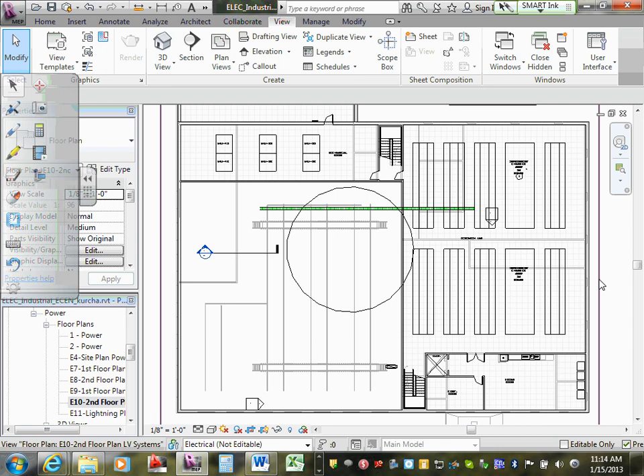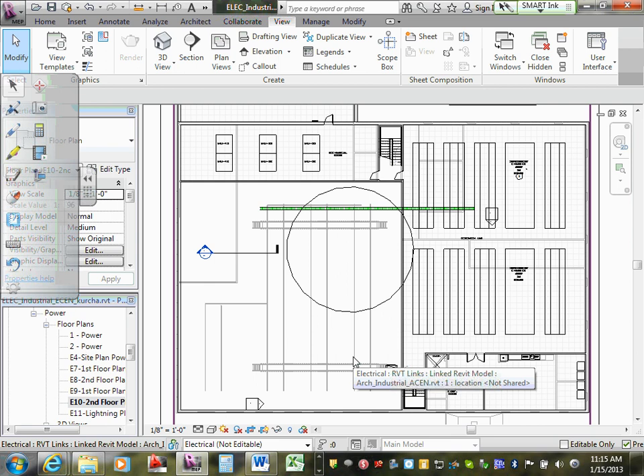Usually it's tied into the building automation, it's tied into the fire alarm system, it's tied into the emergency manual spill system, so it's all tied into all of those systems. So that if one of them were to hit a button, a scrolling message comes out and a blinking light, so they either get out of there, or they know they have to stay in place because they have their own ventilation system. But if it's in each bay, each bay has to act independently of the other one as well. So there's a lot of cross coordination and wiring that goes into this.